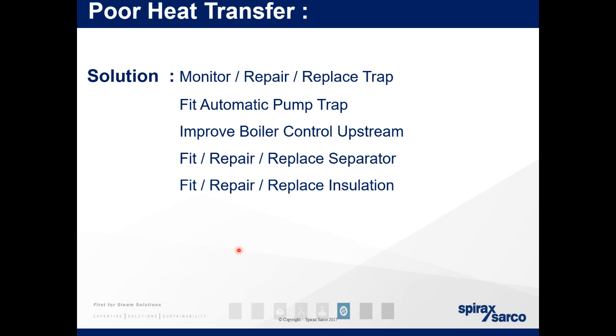So therefore there's less heating time, less energy used to heat that water in the boiler, and less chemical treatment, because remember, this condensate has already been treated. You've already removed a lot of the harmful components you get from the hard water that's coming in as feed water from the mains. So by returning the condensate, even when the majority of it is flash steam, you're reducing the cost of chemicals, the energy that you use, thermal shock to the boilers, all those kinds of things. So the more condensate you can return, the more energy efficient your system is.